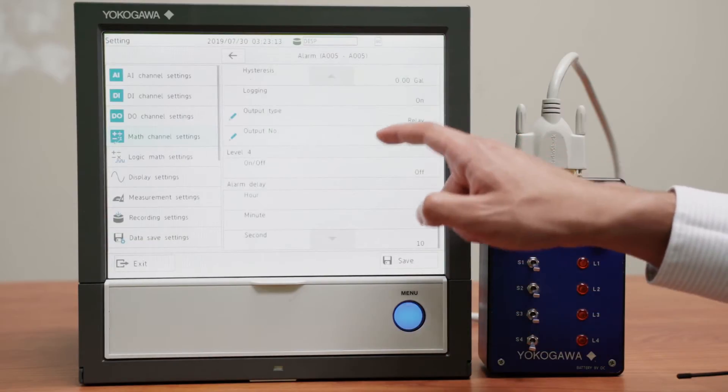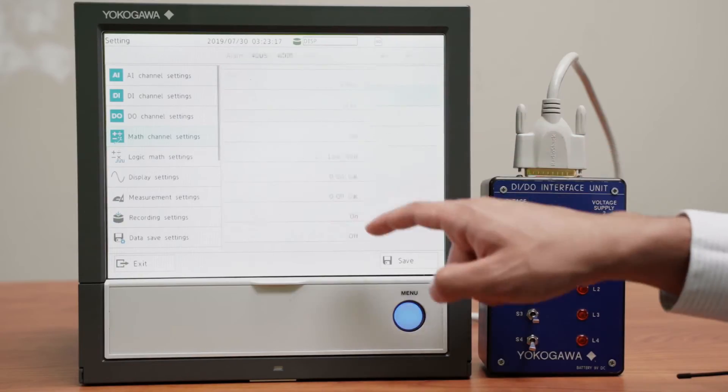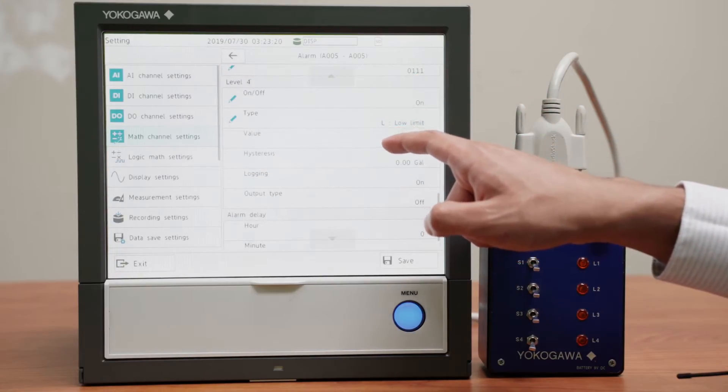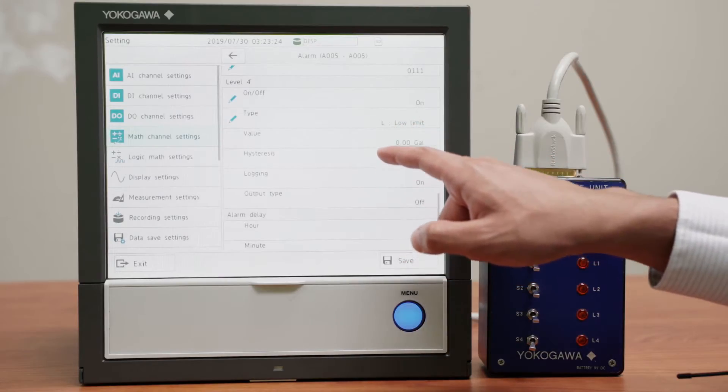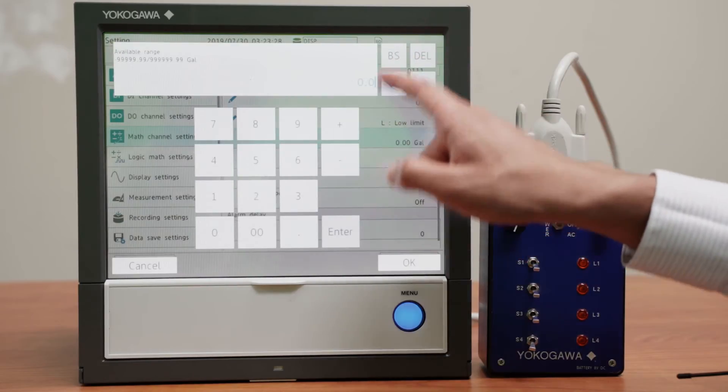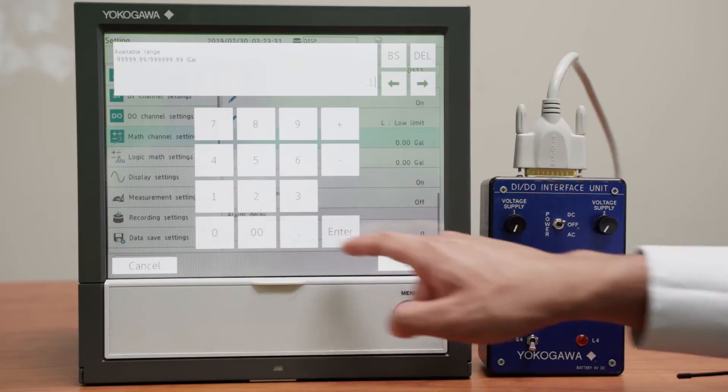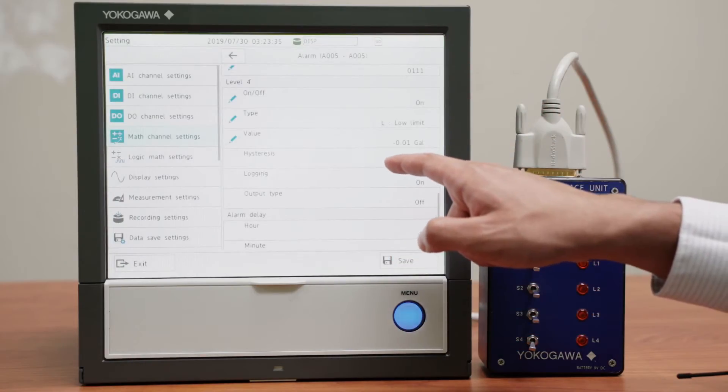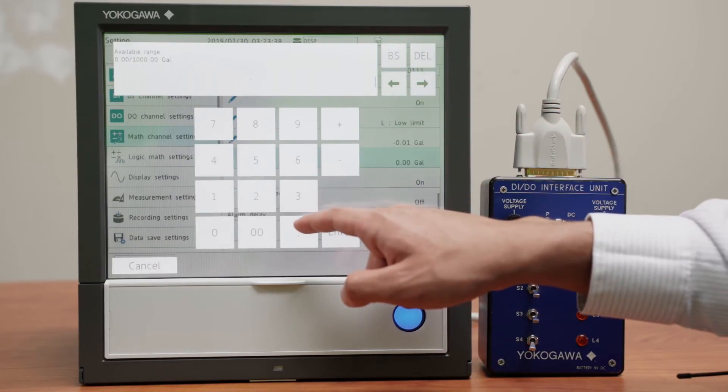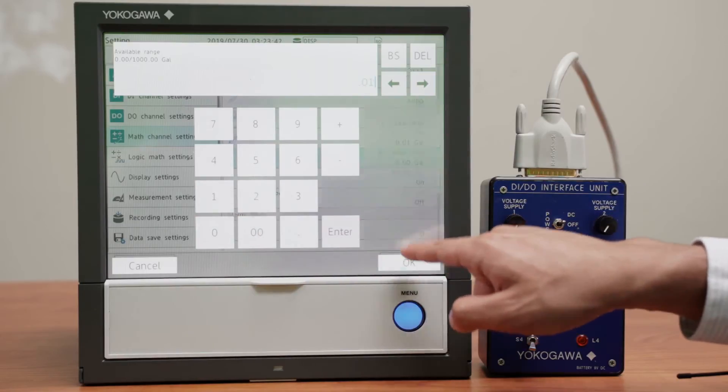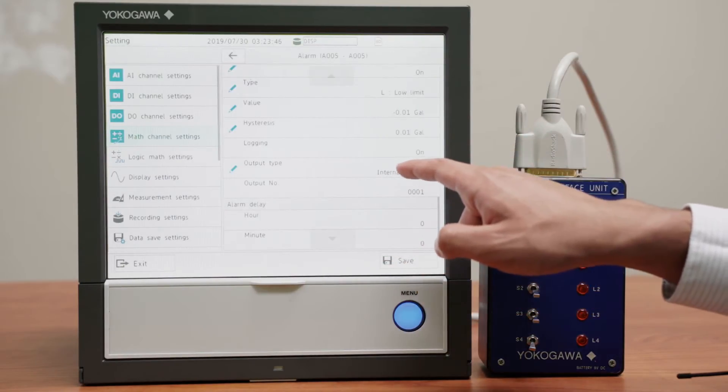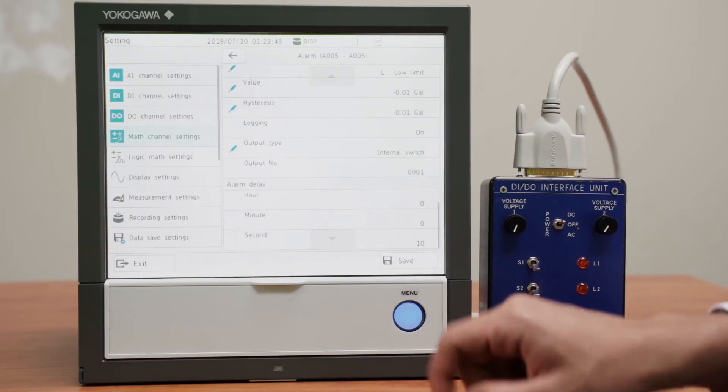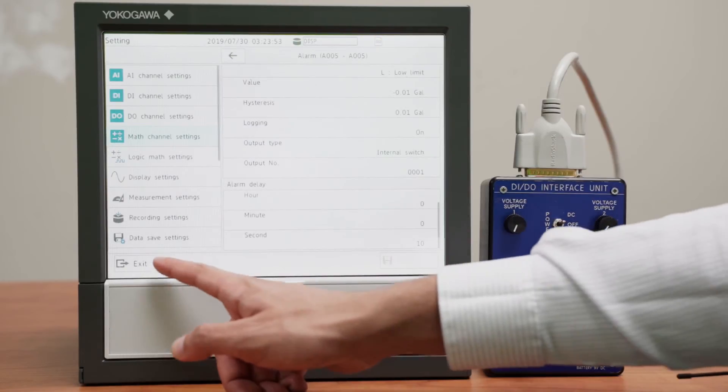And finally we will have an internal switch turn on whenever the value of channel A5 is less than zero. So the value will be at, let's make that negative 0.01, which is the lowest negative number. And we'll have that turn back off when it's zero, so our hysteresis will be 0.01. And our output type will be an internal switch, and it will be internal switch number 1, which we used in the other channels as S1. Now we save that.